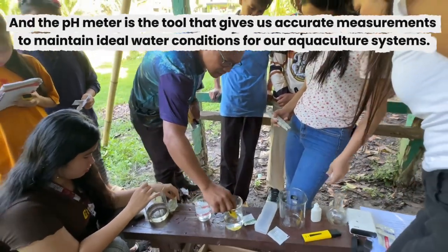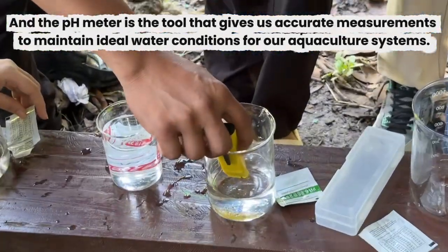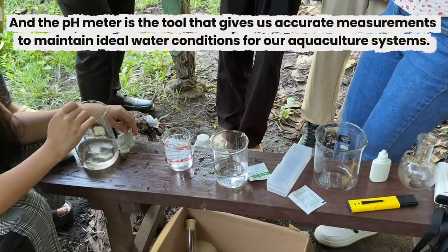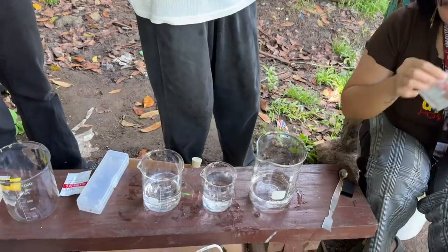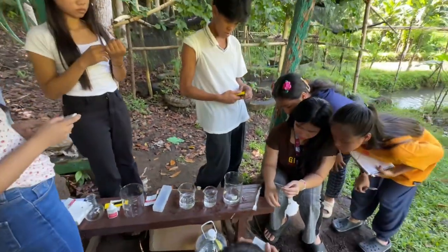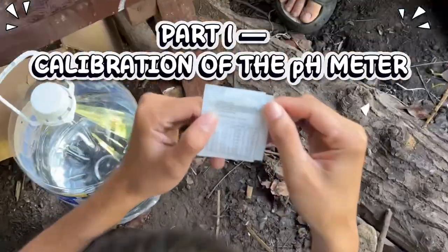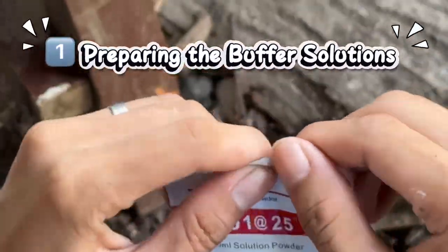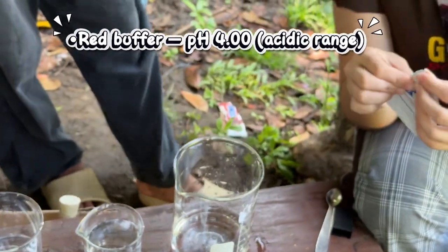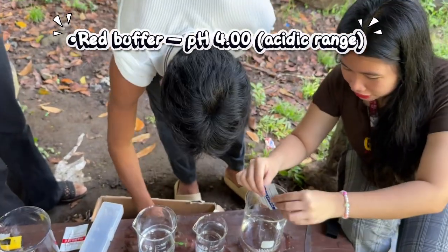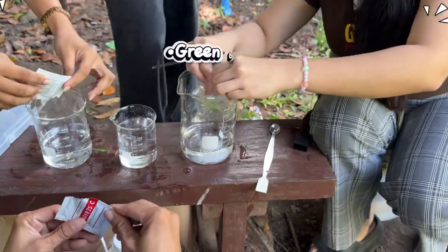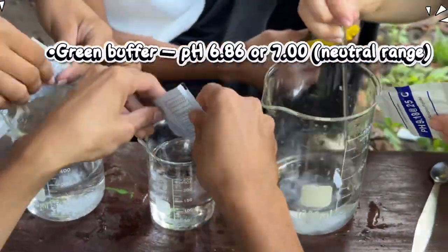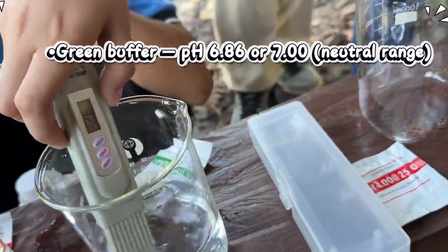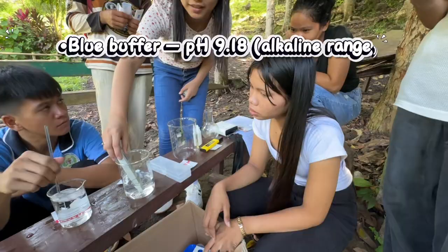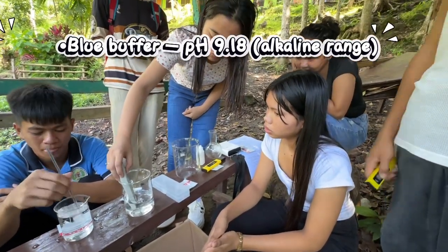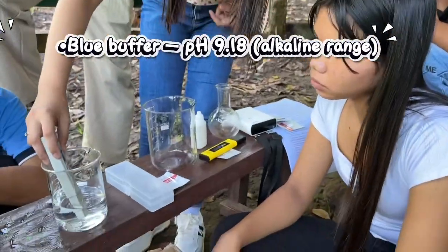And the pH meter is the tool that gives us accurate measurements to maintain ideal water conditions for our aquaculture systems. To get accurate readings, we must calibrate the pH meter using the three standard buffer powders. Red buffer is 4.0 pH level or in the acidic range. Green buffer belongs to the 6.86 or 7 pH level, which belongs to the neutral range. And blue buffer powder belongs to the pH of 9.18, which belongs to the alkaline range.